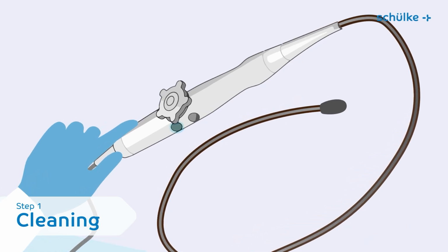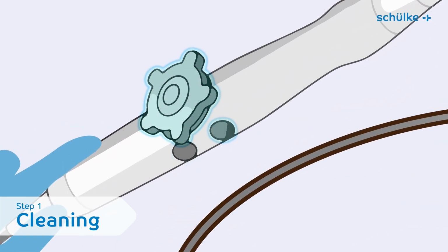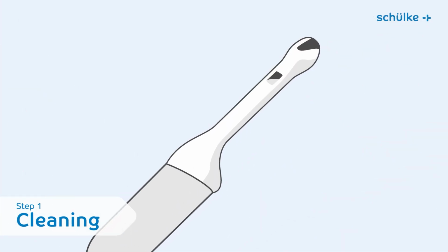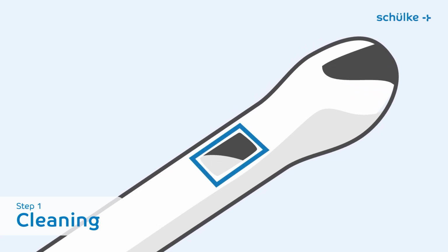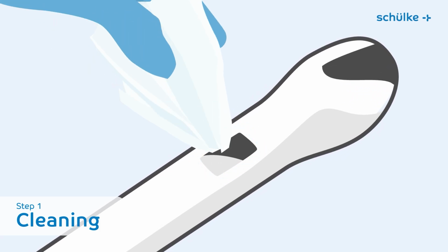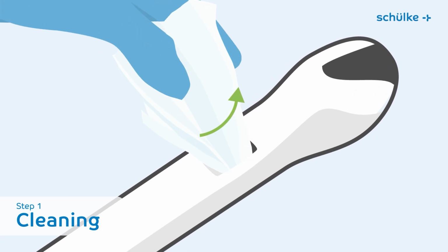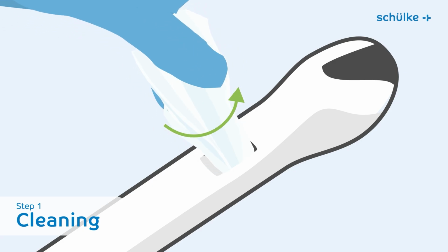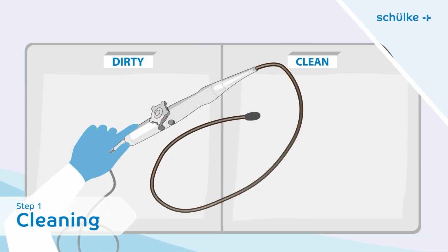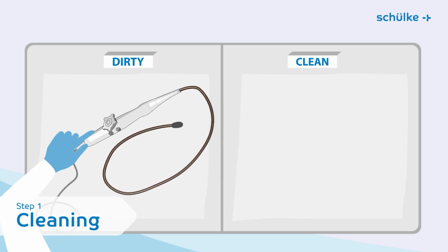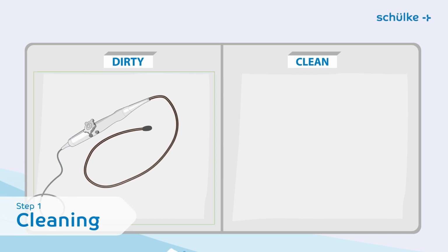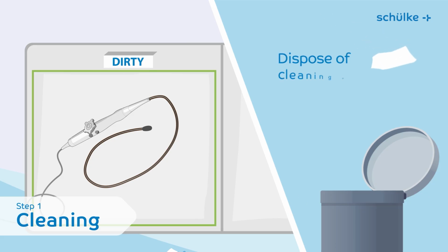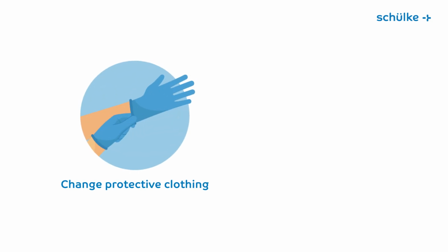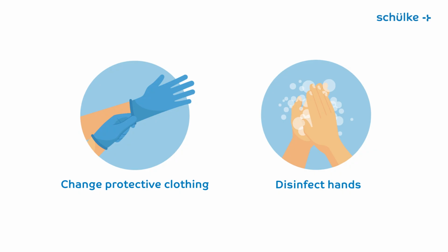Pay particular attention to joints, edges, and recesses. Hard-to-reach recesses on the medical device should be cleaned additionally. To do this, press a tip of the wipe into the recess 5 times in a rotating motion. After cleaning, avoid resoiling of the medical device, for example, by placing it in a clean holder or using a sterile pad. Dispose of the used cleaning wipe in accordance with local regulations. Change protective gloves and carry out hand disinfection.